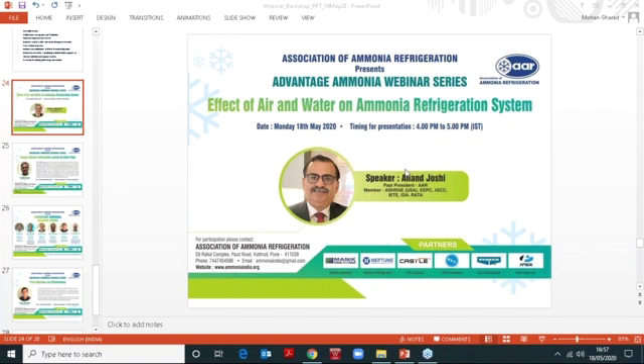Our ammonia system is a closed loop system. So when you are vacuuming a refrigerant plant, it should not affect ammonia. Your ambient temperature should not affect the vacuuming process. It's a closed loop system. You are vacuuming, removing the water and the air from inside the plant. It should not affect your ambient condition. This question is related to removing air using nitrogen gas during the pressure system.